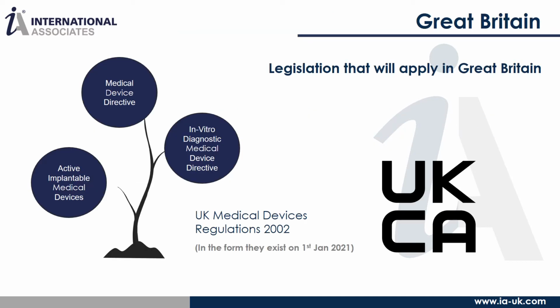In terms of the legislation that will apply, there will be a new route to compliance and product marking called the UKCA mark, which can be used on a voluntary basis from the 1st of January 2021. The requirements for placing a product on the market with a UKCA mark will be based on the UK Medical Device Regulations 2002, which transposed the 3 EU device directives MDD, AIMDD and the IVDD. Legislation is currently passing through government, so this will be in place by January the 1st.